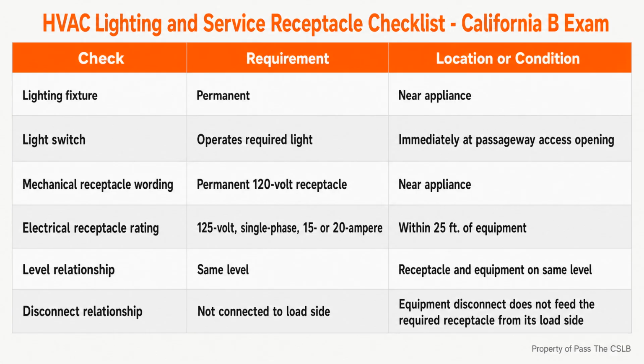I want you to hear one more distinction. Near the appliance and within 25 feet are not interchangeable phrases. The mechanical and electrical provisions use different wording. A general B contractor should avoid casually merging them into a single made-up distance. Verify the actual installation against the applicable provisions and approved documents.